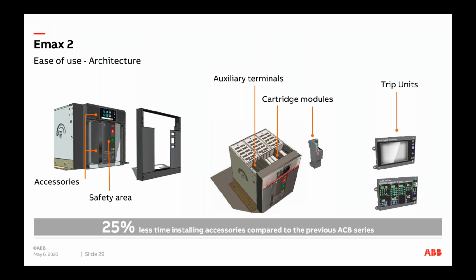Then we have ease of use. The Emax 2 circuit breaker is made quite simple in terms of its architecture. The cartridge modules fit on the top of the breaker. The accessories like shunt opening and shunt closing go on the right side. The motor operator goes on the left side. The trip units are interchangeable. So at any point of time, if there's a damaged screen or you'd like to have a higher level of trip unit, it's almost a plug and play device. Two screws out, and then you can change the trip unit. Cartridges are interchangeable as well. So if there's a change in protocol, it can be easily changed.